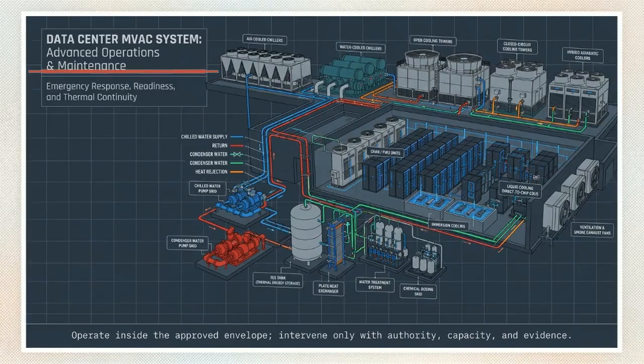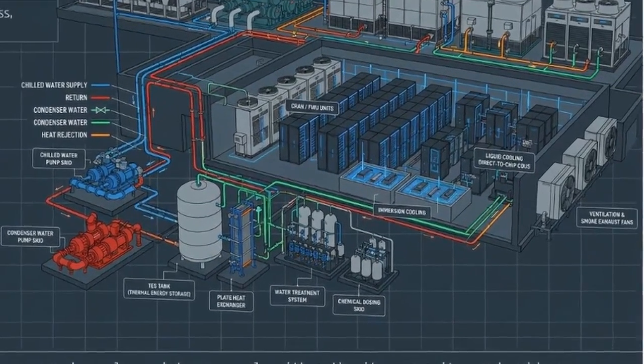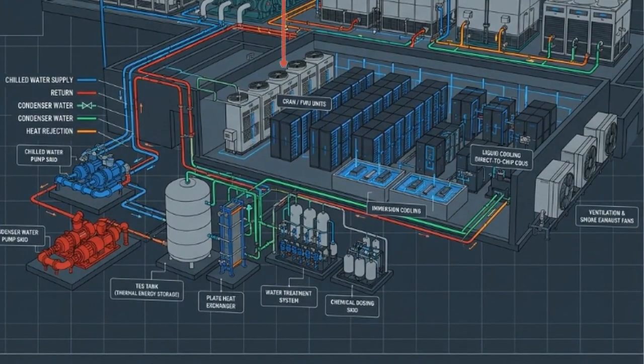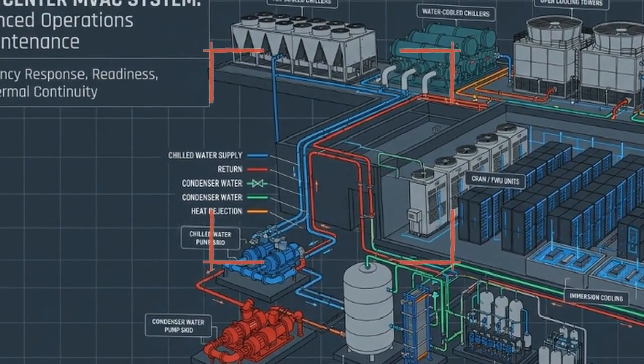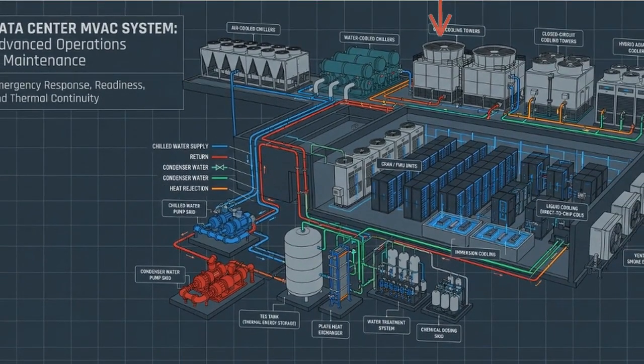This diagram maps the physical inventory of the thermal service path. Heat moves from the IT load demand through liquid-to-air terminal units like computer room air handlers and into the primary and secondary hydronic distribution loops. From those loops, the heat transfers to the rejection plant at the outer edges of the system, utilizing air or water-cooled chillers, and eventually expelling into the atmosphere through open or closed-circuit cooling towers.